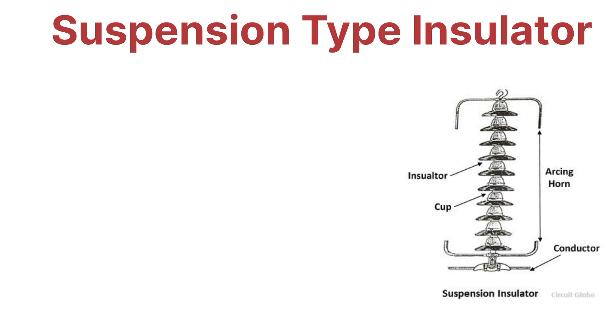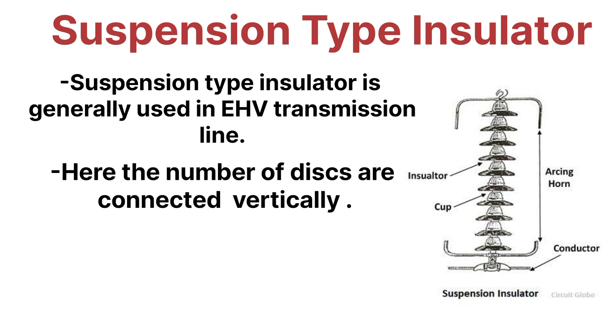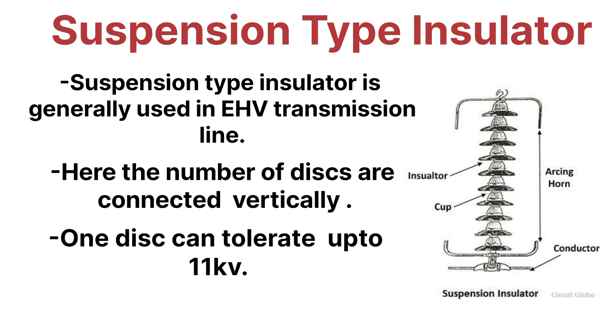The next type is the suspension type insulator, which is used in transmission lines, particularly for extra high voltage lines. A number of discs are connected vertically for the transmission line, and one disc can tolerate up to 11 kV. You can recognize these in overhead transmission lines where discs are connected vertically to the tower.